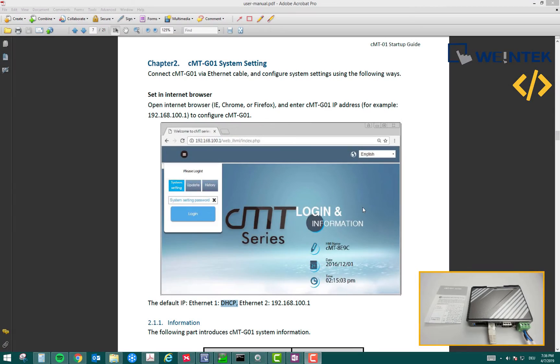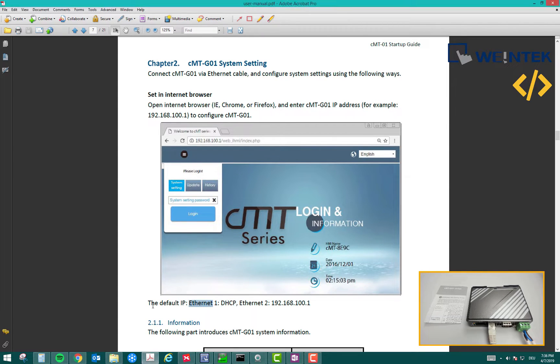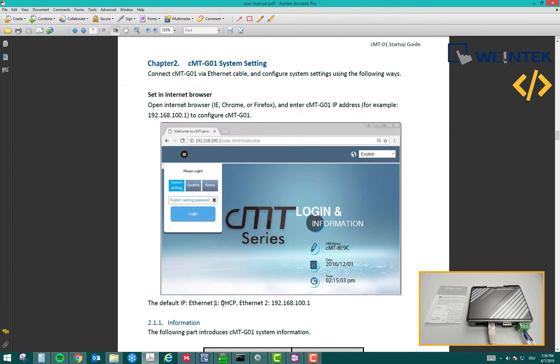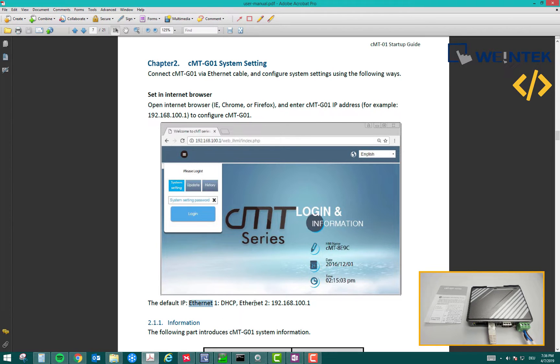Now we will access the web interface. If you check the user manual for this device, there are some important instructions for the connection. If you're connecting to Ethernet1, the default IP says DHCP. DHCP means it will look for the IP address in the network and the network will automatically assign the IP address to Ethernet port 1. If you connect Ethernet port 2, the default IP is 192.168.100.1.